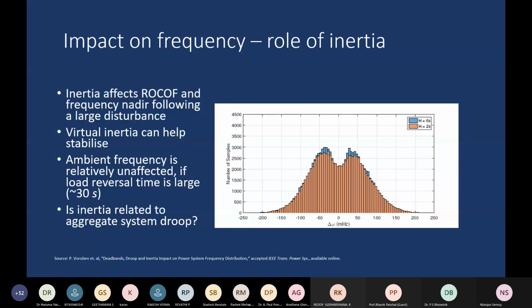That is the frequency. When we talk about the frequency change because of an event, the inertia affects the rate of change of frequency, which is also referred to as ROCOF. So if you have a low inertia power system, the frequency changes at a very high rate, so the ROCOF is very high. Similarly, the nadir, which is the lowest point in the frequency, also becomes much more pronounced when the inertia is low. So how can we improve the situation? We can improve it by introducing more and more virtual inertia.